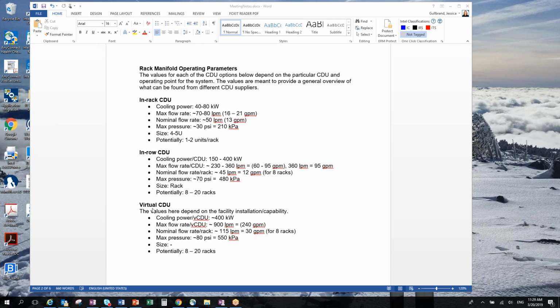What I've found so far for in-rack CDUs: cooling power of 40 to 80 kilowatts, with max flow rates of 70 to 80 liters per minute, nominal flow rate of around 50 liters per minute, with a max pressure of 30 psi. And the size of the in-rack CDU is about, depending on the supplier or manufacturer, 4 to 5 U's.